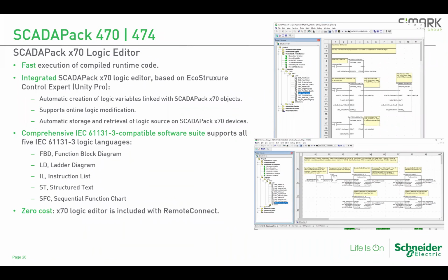Along with Remote Connect, you get a Schneider Unity-based logic programming engine. This is not ISaGRAF - it does support the IEC languages, but it's wholly owned and supported in-house by Schneider. We're reusing the work done in the software used to configure the higher-end Modicon PLCs, now at the RTU level. So you get that power and familiarity if you've already used Unity, working for you in the SCADAPack RTU. It supports 5 different languages, and it's all included as a free download with no licensing required to utilize this software.